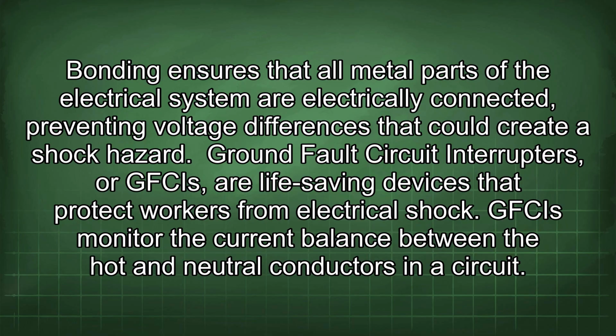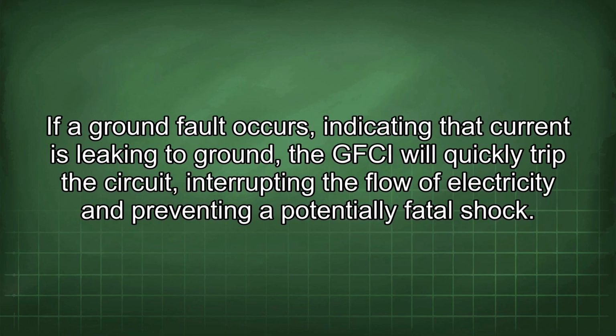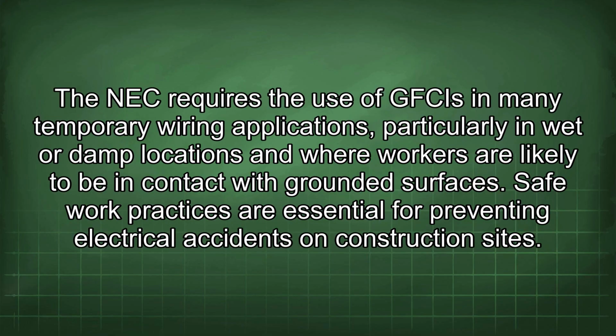Ground fault circuit interrupters, or GFCIs, are life-saving devices that protect workers from electrical shock. GFCIs monitor the current balance between the hot and neutral conductors in a circuit. If a ground fault occurs, indicating that current is leaking to ground, the GFCI will quickly trip the circuit, interrupting the flow of electricity and preventing a potentially fatal shock. The NEC requires the use of GFCIs in many temporary wiring applications, particularly in wet or damp locations and where workers are likely to be in contact with grounded surfaces.